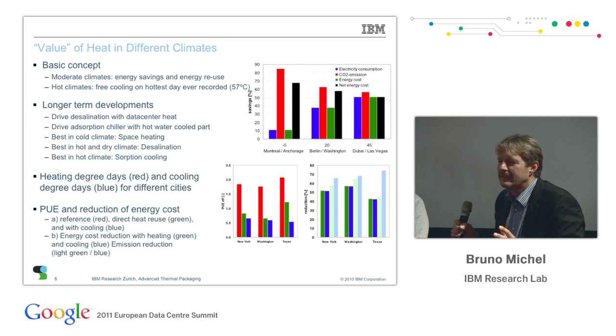But nobody wants to heat. Now, we were looking, are there consumers of heat in a hot climate? Yes, there are. Desalination needs a lot in a dry climate. Yeah. And the second is we can convert heat into cold with a process known as adsorption chiller. And adsorption chillers, luckily, don't need too high a temperature. They can live with 75 degree temperature, and that's our target for the next generation. Have about 65 to 75 degree output, so that we can produce cooling for a legacy part of our data center. As long as our hot water cooled components are 80% of the data center, we can cool the rest.